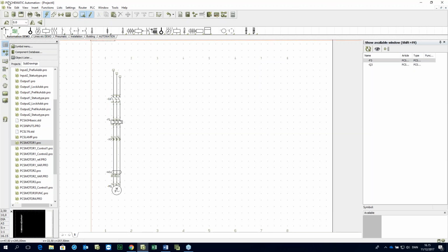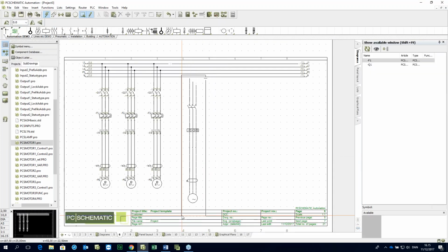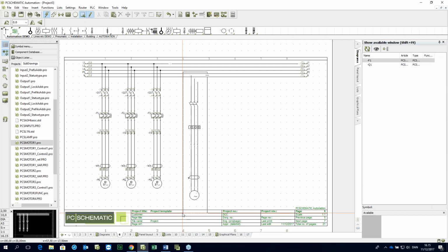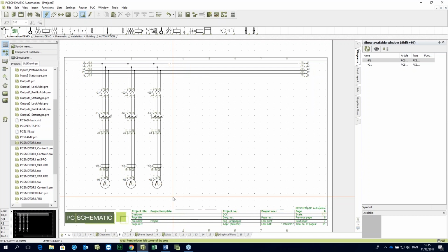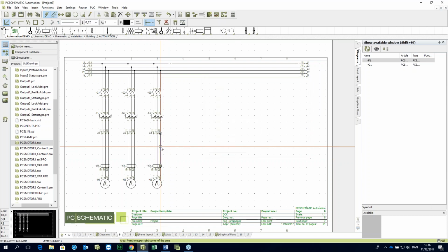So that's the main reason that when I make new subdrawings, I would never copy anything and say that this is my subdrawing, not directly from the project. Another reason why I don't just want to open an old project is that there might be a lot of hidden things in an old project. If you didn't make it yourself, you don't know anything about what's actually in it. And sometimes we have seen that there might be double lines, or non-conducting lines, or lines with data in them.